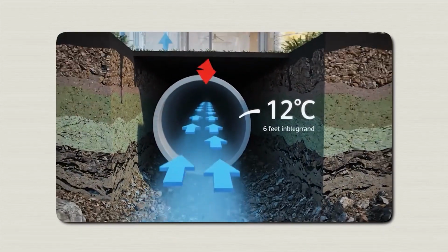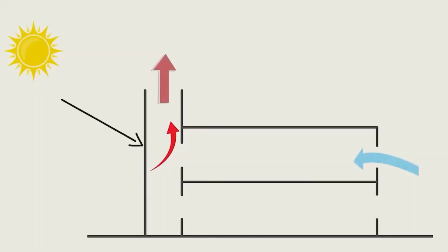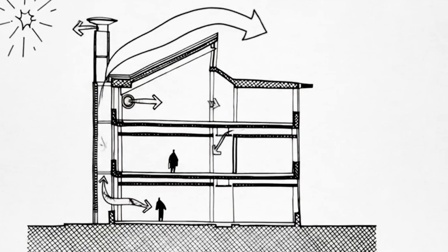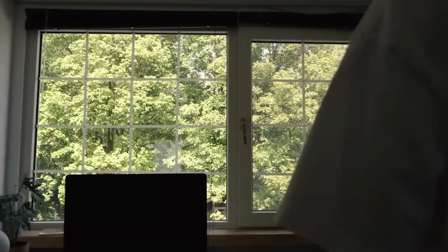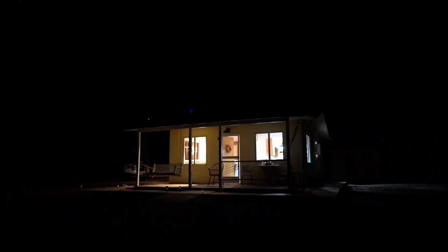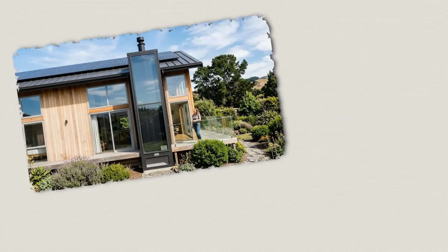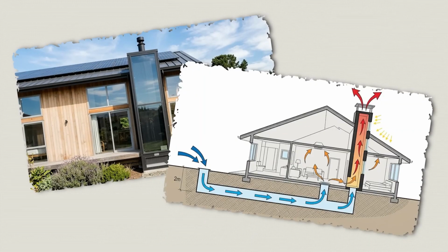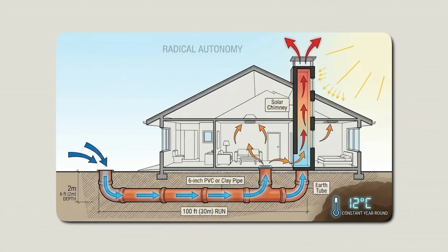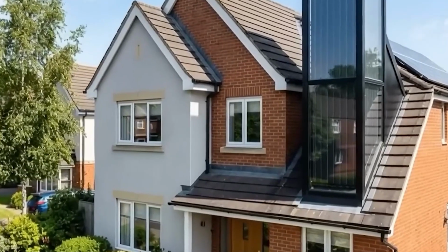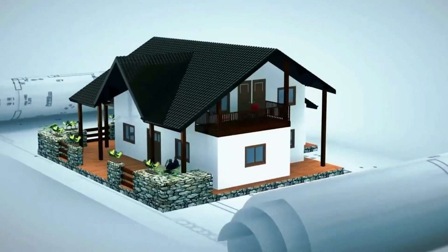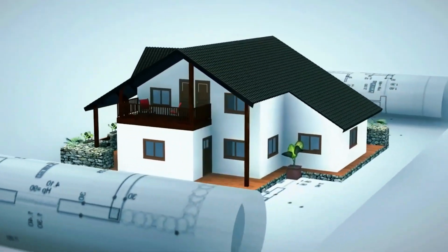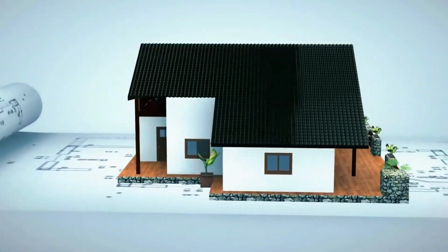As the research literature notes, sustained use over days and weeks gradually warms the soil immediately surrounding the pipe, which narrows the temperature differential and reduces performance. This is manageable through intermittent operation, running the system during the hottest parts of the day and allowing the Earth to recover overnight, but it is a constraint that a purely mechanical system does not have, and an Earth tube is not a retrofit you can implement in an afternoon. Proper installation requires excavation. That cost is real and needs to be factored into your payback calculation honestly.